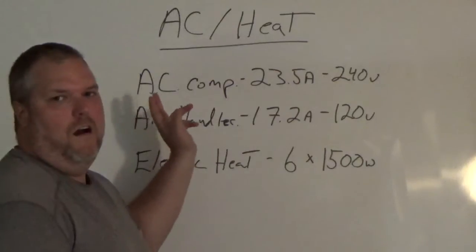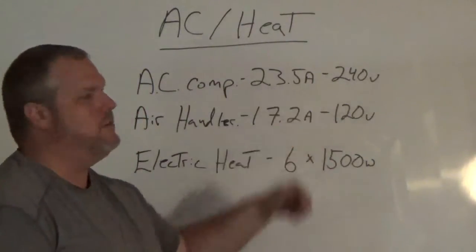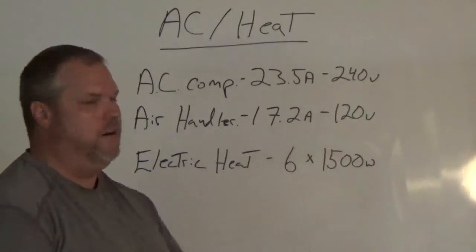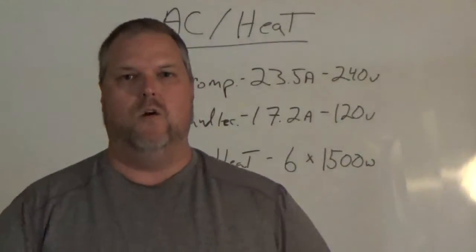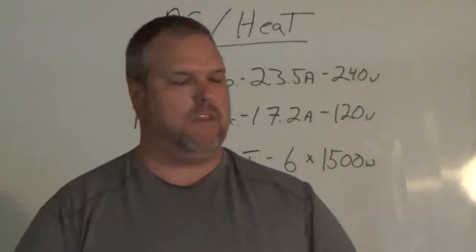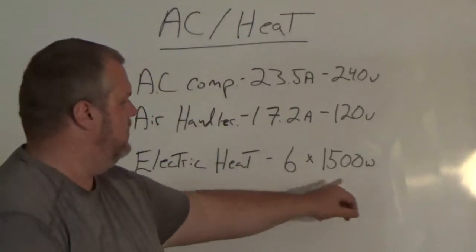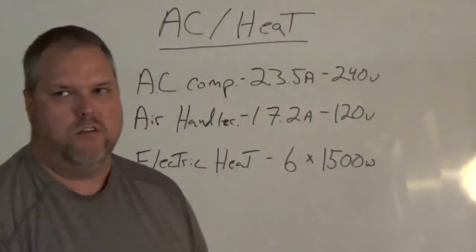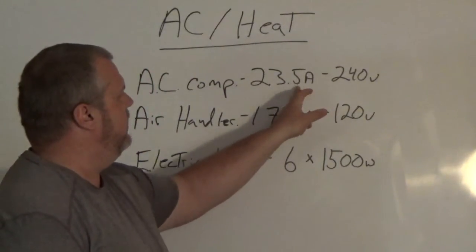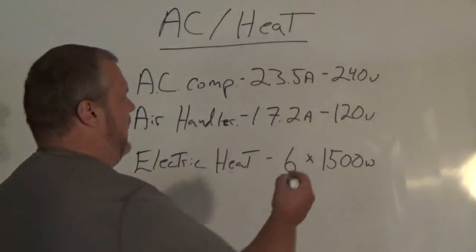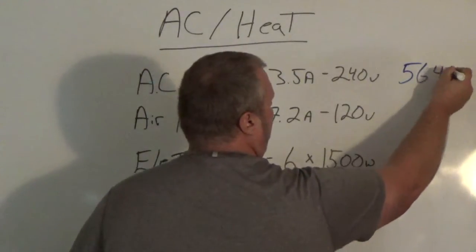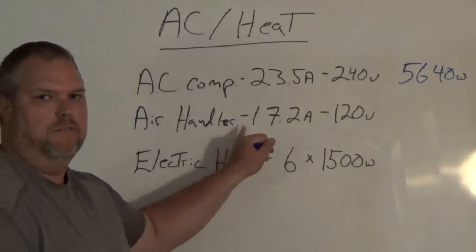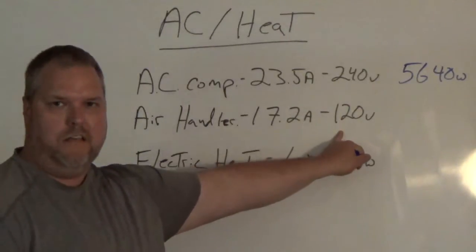AC compressor: 23.5 amps at 240 volts, very common. Air handler: 17.2 amps at 120 volts. In this case, the air handler is strictly used for AC. The electric heat: we have six pieces at 1500 watts apiece. All we're going to do is simple Ohm's law. We calculate 23.5 times 240 and we get 5,640 watts.